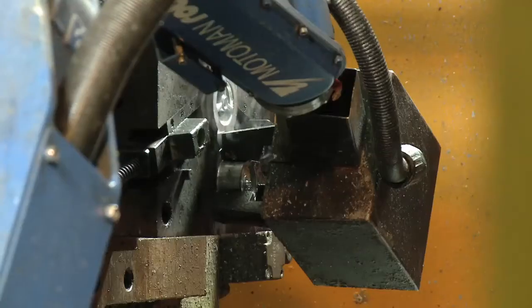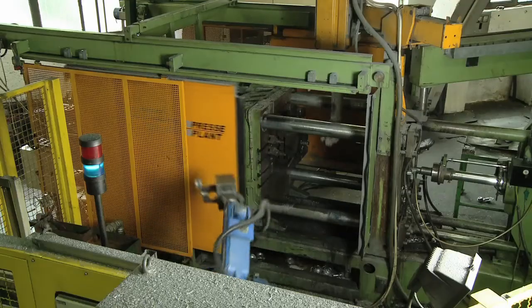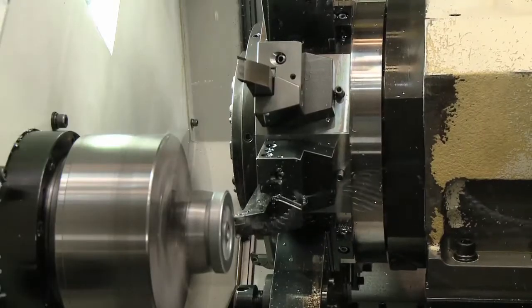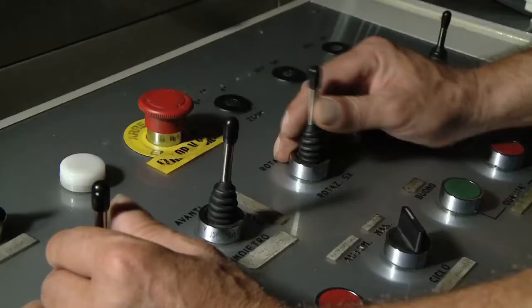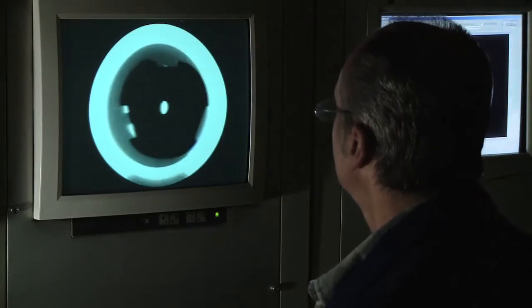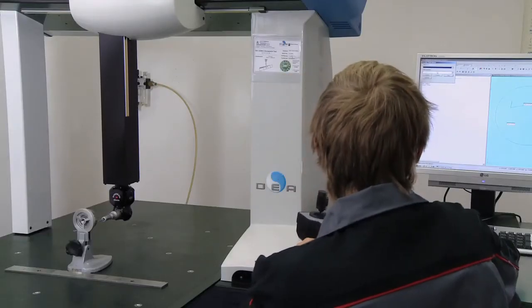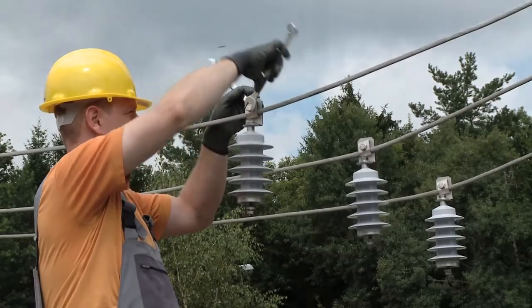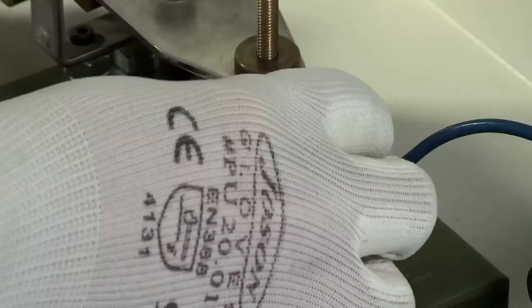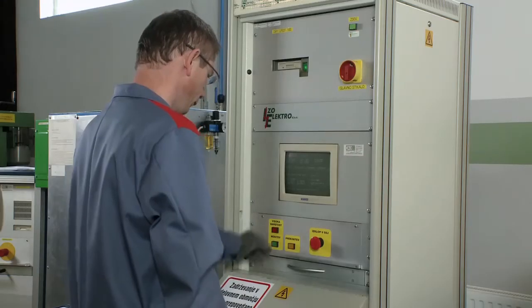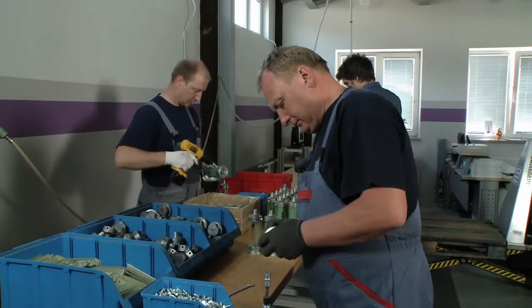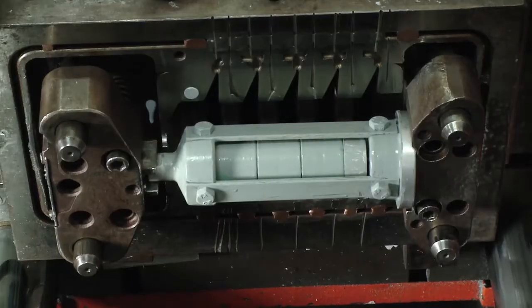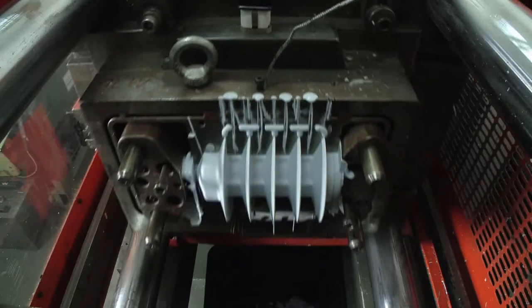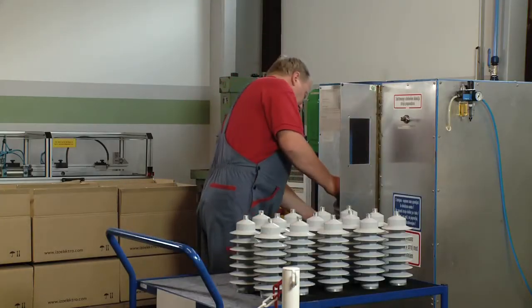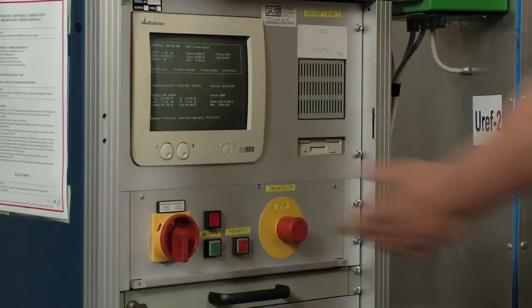We also produce Class 1 medium voltage metal oxide surge arrestors up to 45 kilovolts. The surge arrestors, type 2SS15N, have been tested in the accredited Italian lab CESI, whereas their top quality is ensured by a low residual current and a specific construction with varistors directly enclosed by silicone. The varistor block is set up on the basis of a given varistor voltage value, measured on a control device. The construction with insulating profiles enables high bending and torsion moments. Once siliconizing is done, all surge arrestors are tested on calibrated devices by performing reference voltage measurements.